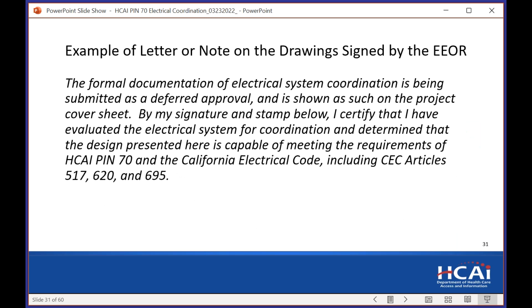All right, next question we have is, does HCAI consider using fuse in lieu of circuit breaker in order to provide proper coordination? This will create more unsafe conditions for patient in hospital in order to restore power due to require fuse replacement. Yeah, well, the code allows you to use fuses. And so we take no exception to using fuses instead of breakers for coordination.